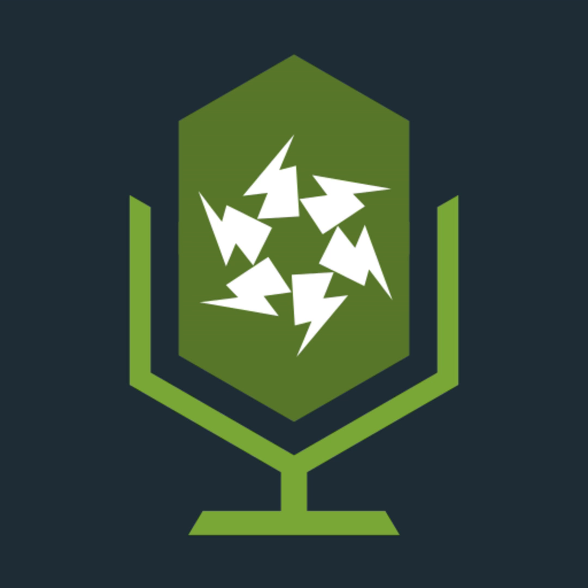Yeah. Right, so again, it's like when we talk to people about PFC testing, people say to us, well, we do an earth loop test, and if we press a button there, it gives us a PFC reading. Well, yeah, it gives you an earth fault current reading. What about your short circuit? And then you have to try to explain to them the difference between earth fault and short circuit, and the fact that you're actually looking at different conductors. I was talking to somebody yesterday because he was looking at a new instrument. He says, yeah, but the problem with this one isn't your loop and your PFCs at the same time. I was like, you don't need them at the same time. You shouldn't be doing the test at the same time. They were like, yeah, but with this one button, you get both.